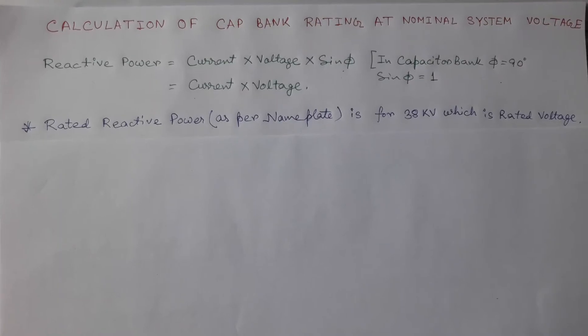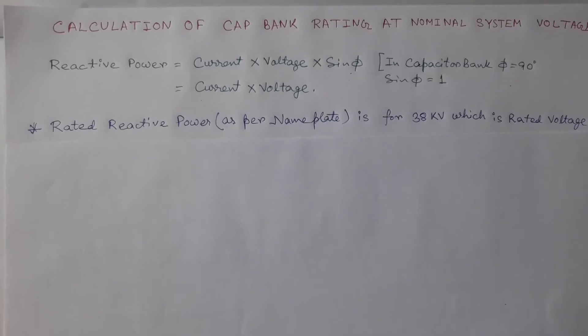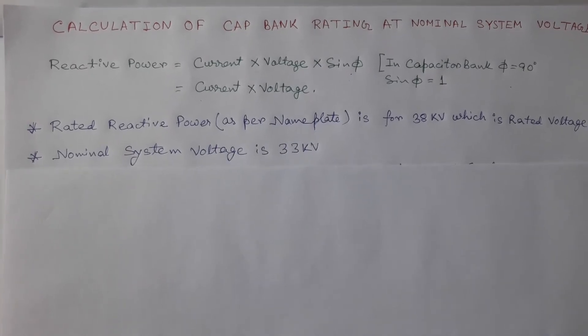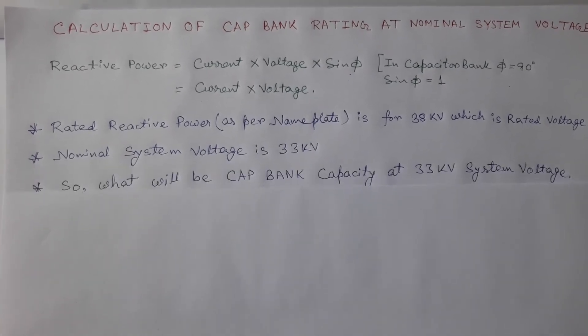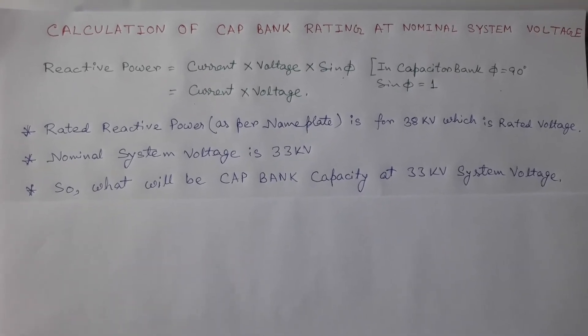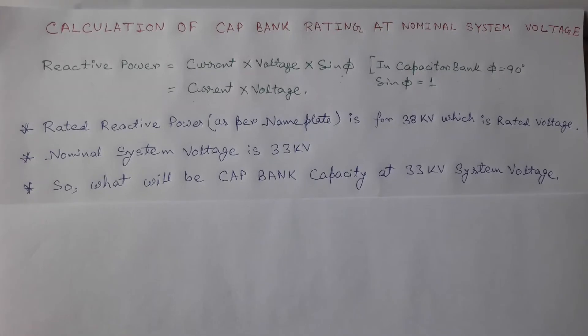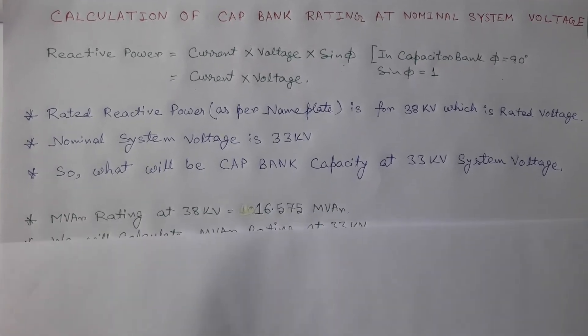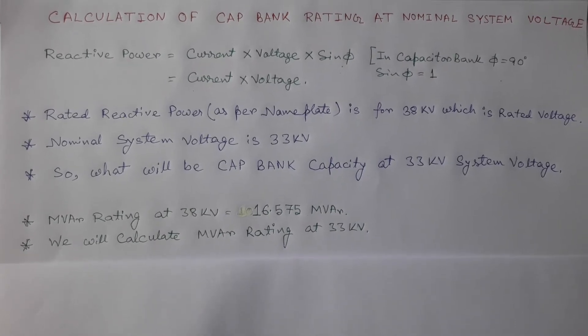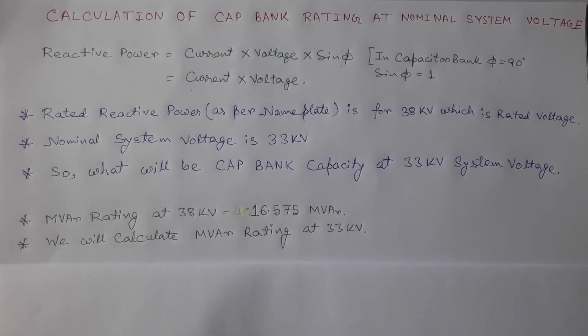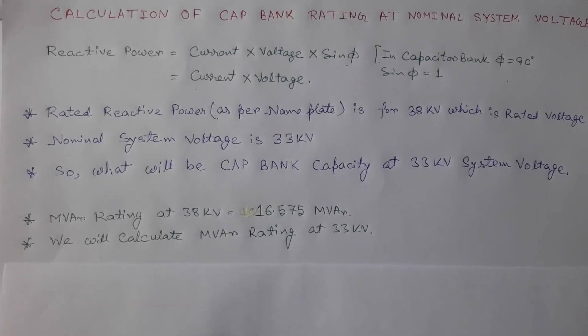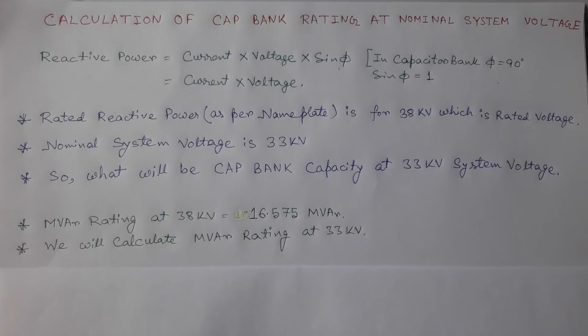As per the nameplate, reactive power data is provided for 38 kV, but our nominal system voltage is 33 kV. So what will be the capacitor bank capacity at 33 kV system voltage? In this example, the reactive power is 16.575 mVar at 38 kV, and we have to calculate the mVar rating for 33 kV system voltage.